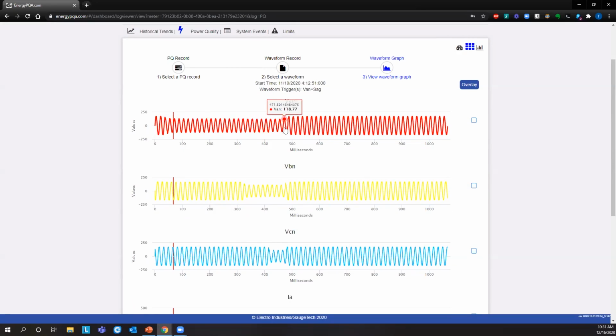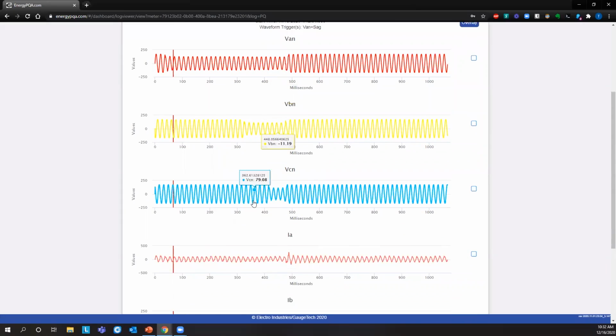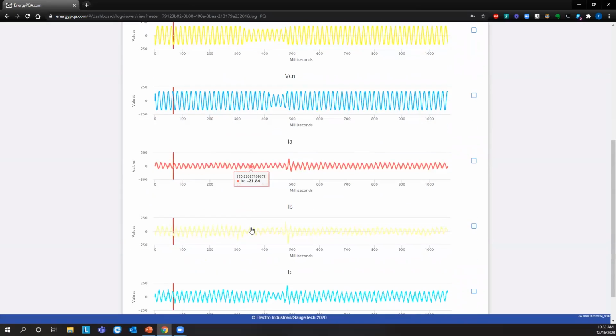If I had any pieces of equipment that failed, I'll know that I need to put some sort of voltage protection on those devices. So if this sag ever happens again, that device is protected and I won't lose it or have to replace it. Here we can also see the effect of the current. So again, no matter what parameter was the trigger, the meter will record all 6 channels. So you can see each phase, voltage and current, what went on.